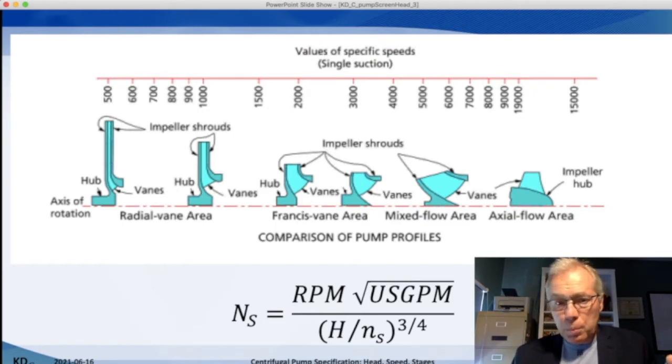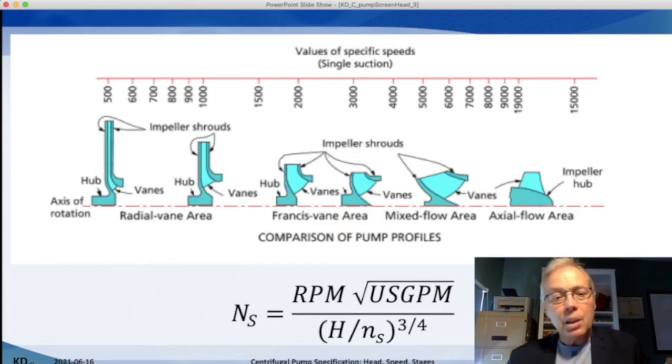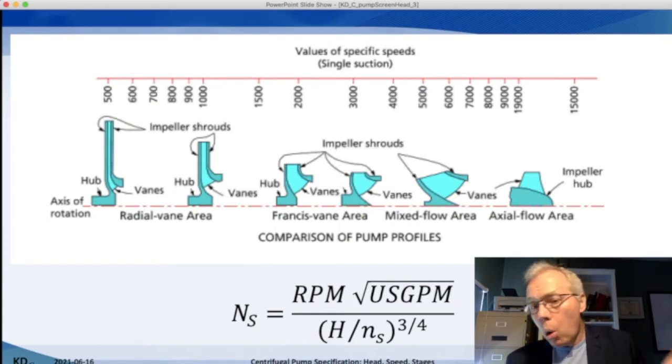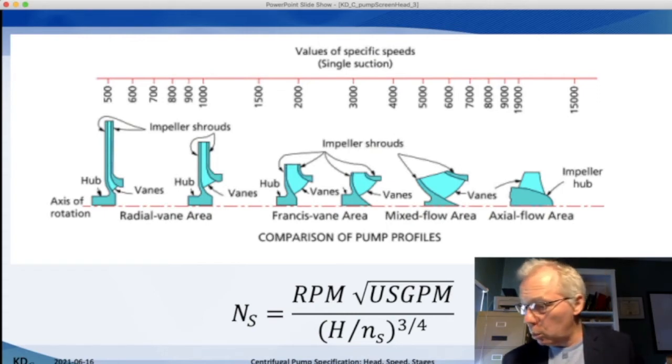Now the specific speed uses the pump speed in RPM, the square root of the flow rate in US gallons per minute, and the head developed by each stage in the pump raised to the three-quarter power. Or, we could say it's the total head generated by the pump divided by the number of stages, all raised to the three-quarter power.